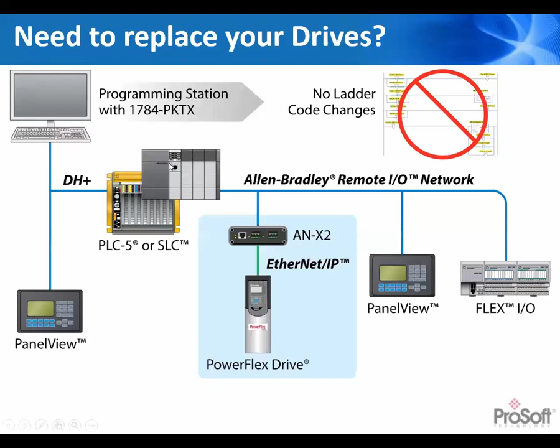It may be that you've looked at the programming stations and SCADA screens, and the PCs there are old boxes with their ISA slots and old processors running older operating systems such as Windows XP or Windows 95, and you need to upgrade those to modern PCs with modern operating systems to run the latest SCADA systems or program packages while still maintaining the older programming package to keep the plant going for as long as possible. With the gateway, you can add in an Ethernet IP network and still use your existing Data Highway Plus network, using your existing PLCs, talking to the existing remote I/O network, but changing over the HMI screens to the latest PanelView Plus systems on Ethernet IP, talking over DH Plus, or even talking directly to the remote I/O network.